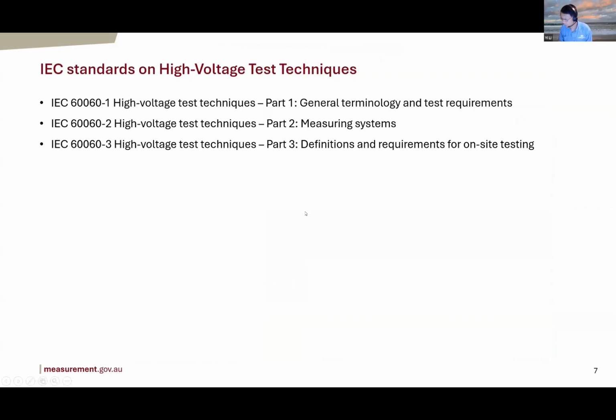Now let's have a look at the specific testing standards which are very important for high voltage testing. This IEC 60060 series is a very top-level general standard that defines the testing terminology, testing procedures, and measurement requirements for all high voltage testing. This particular standard is about partial discharge, which is also important. You don't see partial discharge normally at a high voltage. I'll backtrack. Partial discharge is for high electric field insulation. In the high voltage field, the electric fields are normally high. That's where you have partial discharge, which is minute discharge in electrical insulation that will eat away the insulation over time. So all the equipment needs to be tested for this minute discharge.